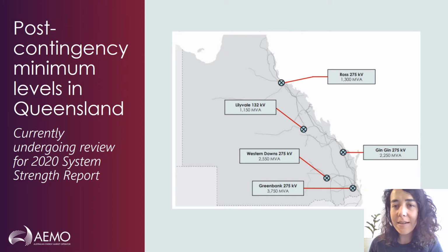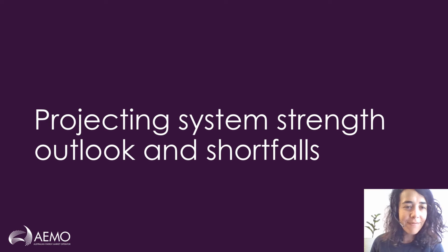So here we see the minimum fault levels that were decided using this process for Queensland. And I do note that right now we are reviewing these levels because we will be releasing a 2020 system strength report later this year. And so some of these may change, but this gives an indication of the fault level requirements across Queensland, which reflect our understanding of system strength requirements. So once we have set those minimum requirements across a region, we turn to project how system strength will look over the coming years and see whether or not there are any shortfalls that need to be addressed.